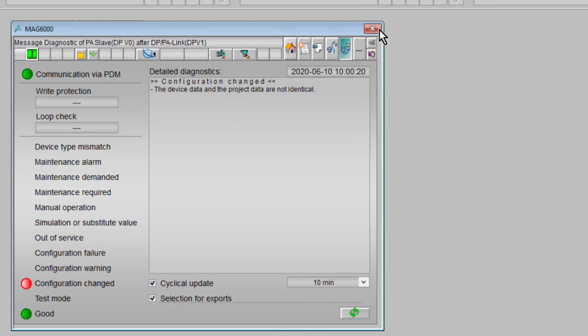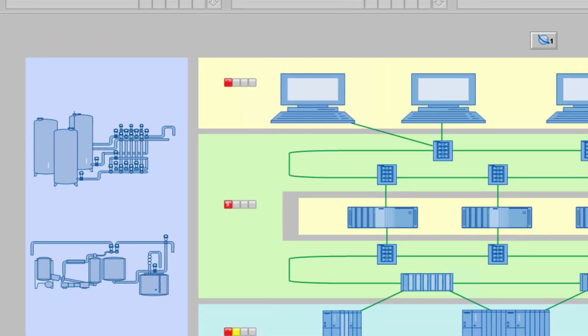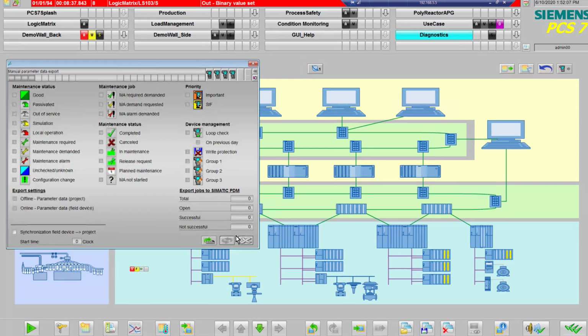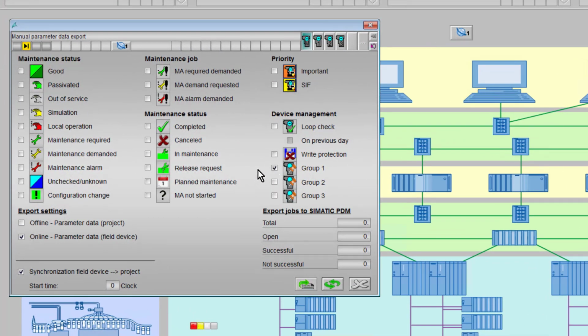So that's done, and then if I go back to here, you'll see the option, and I've already got one set up to do every hour to read everything that's ticked for exports in group one, regardless of the status. Look, I've got nothing else ticked, and that will then send those parameters to a storage location on your PDM maintenance station, and then you have some software that sends those XML reports off to the Citran SamIQ app, which then visualizes and trends all of that data.